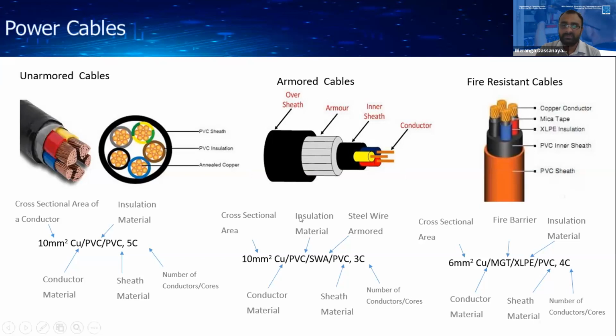So the difference between these armored cables is when you are denoting after the insulation material, you are using the notation SWA for steel wire, telling that it is a steel wire armored cable. Here you can see there are 3 conductors inside this cable. So we are putting 3C after all these things.